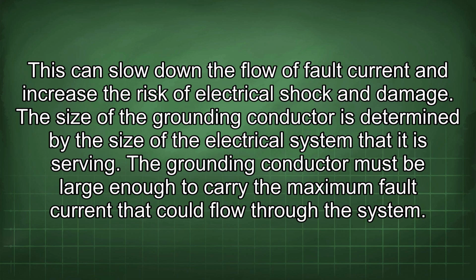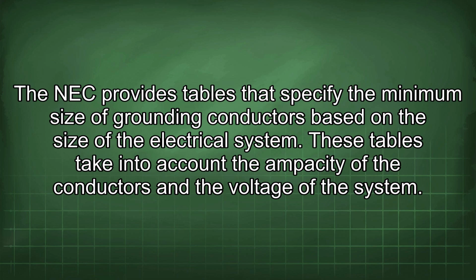The size of the grounding conductor is determined by the size of the electrical system that it is serving. The grounding conductor must be large enough to carry the maximum fault current that could flow through the system. The NEC provides tables that specify the minimum size of grounding conductors based on the size of the electrical system. These tables take into account the ampacity of the conductors and the voltage of the system.